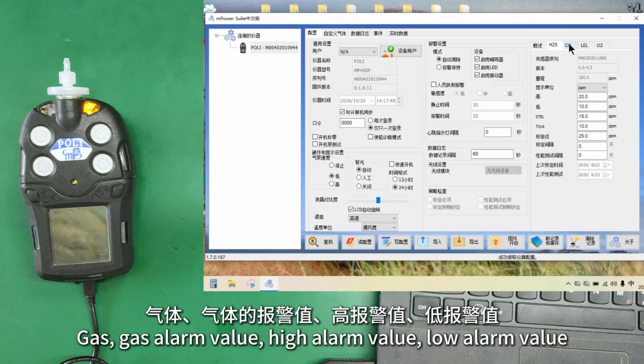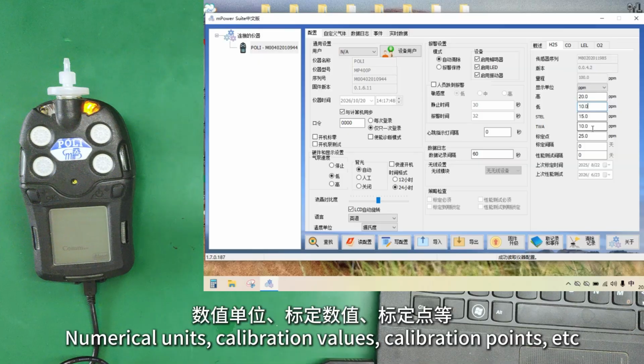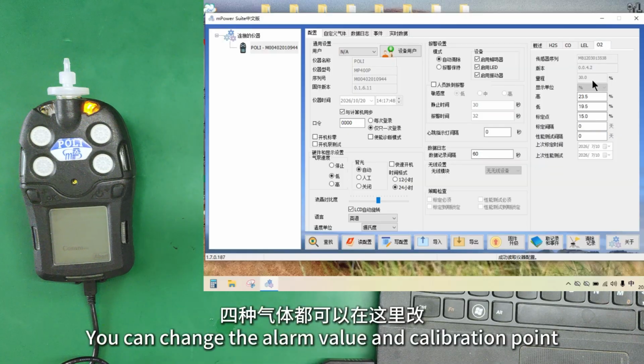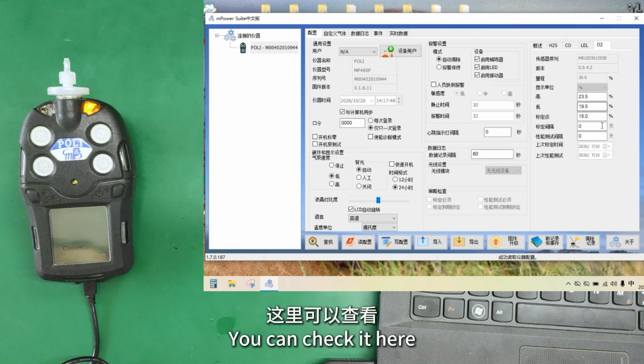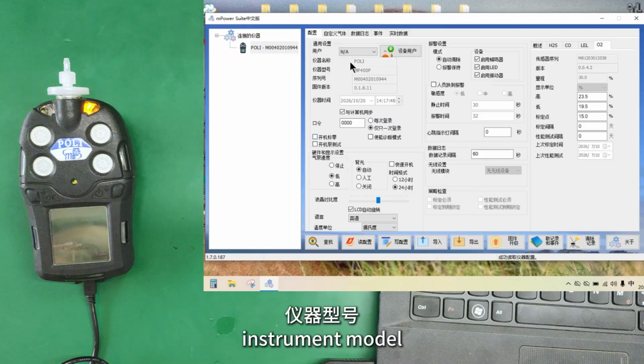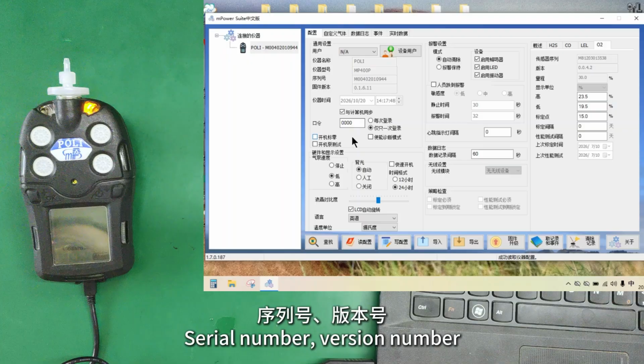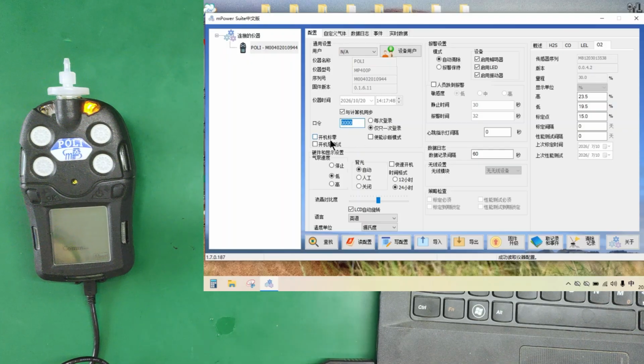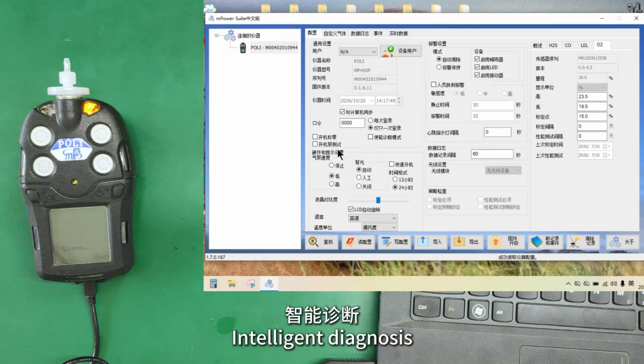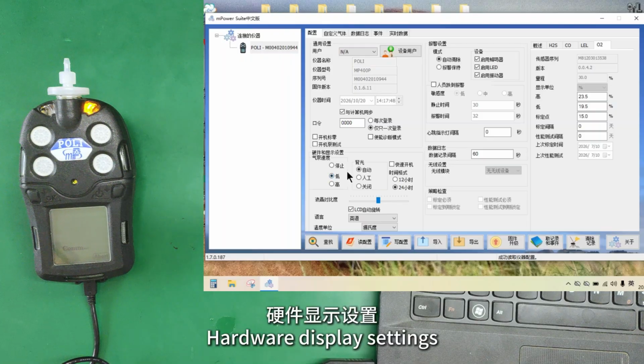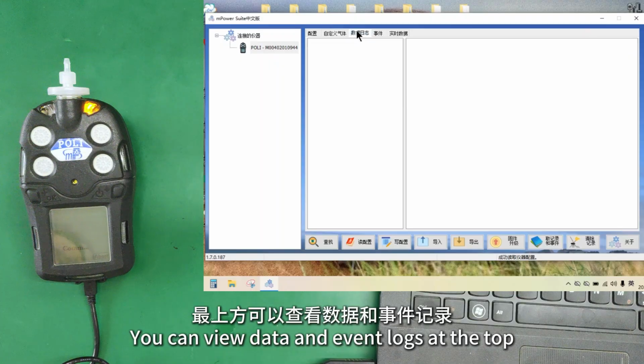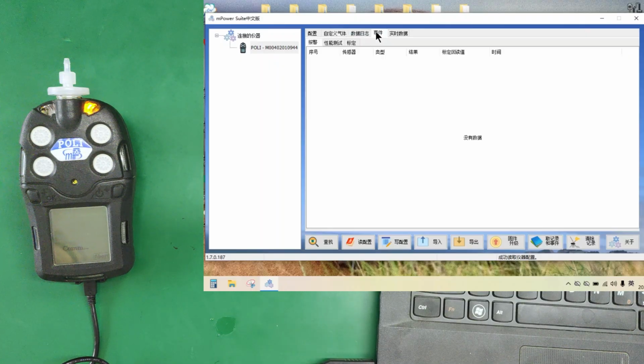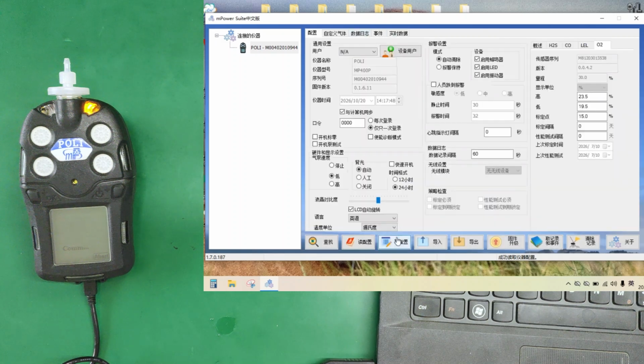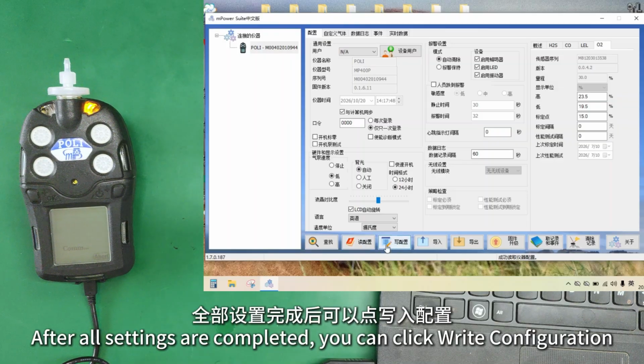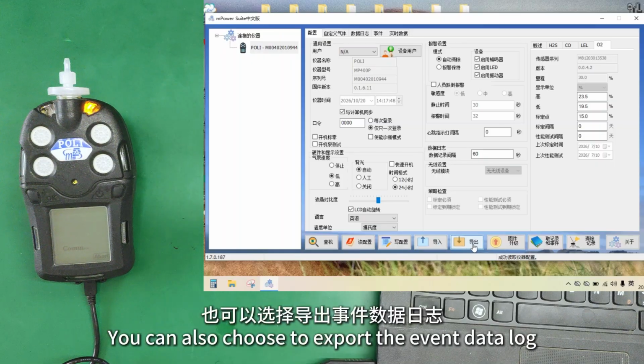Gas alarm value, high alarm value, low alarm value. Numerical units, calibration values, calibration points, etc. You can change the alarm value and calibration point. You can check it here. Instrument name, instrument model, serial number, version number. You can change the menu password here. Select whether to turn on the zero mark, intelligent diagnosis, startup, pump test, hardware, display settings. You can view data and event logs at the top. After all settings are completed, you can click Write Configuration. You can also choose to export the event data log.